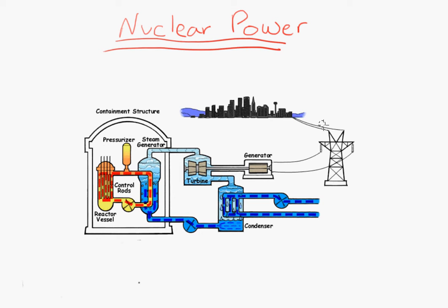So we'll do that by running the steam through another kind of heat exchanger that we call a condenser. And the condenser, as you may guess, condenses steam into water. It's fueled by this independent source of water here, which is often just off-site water, either seawater or just fresh water, depending on where the plant is installed. So it's cooled down and it condenses into water. And now a feed pump moves that newly transformed water back into the steam generator.